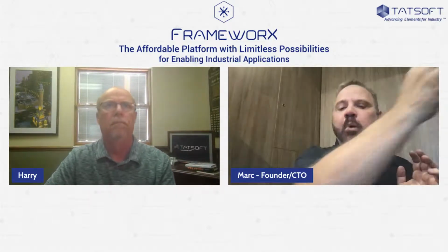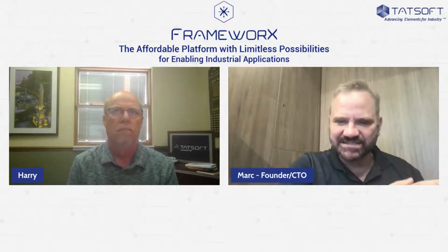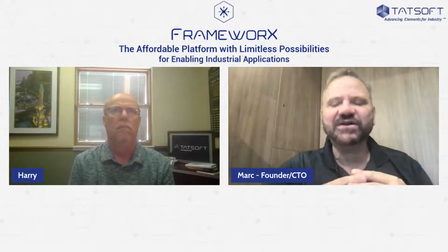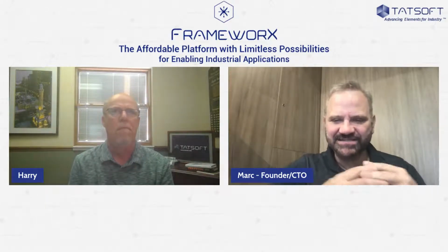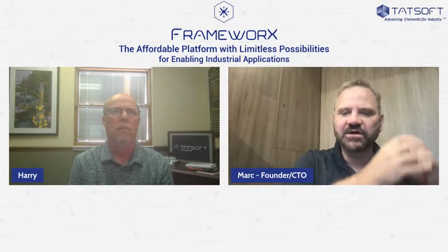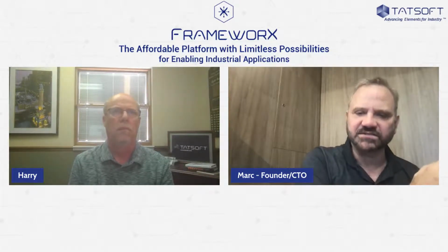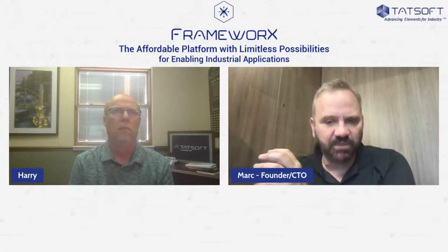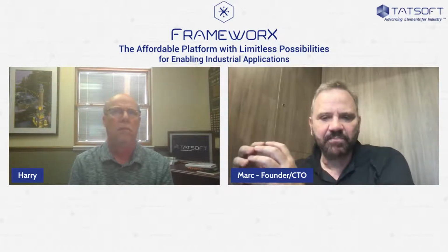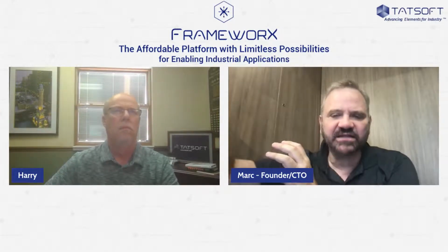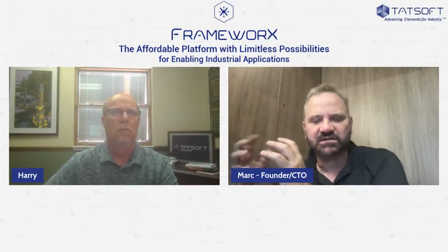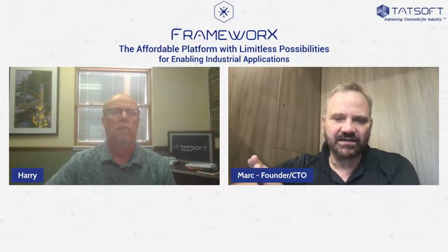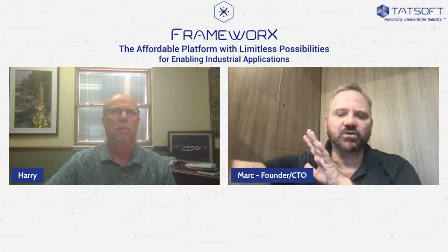And you can even import the definition, but essentially, after importing that definition, I hold the keys for that definition. I have that instance defined in my tag model with my connection to the external data source.